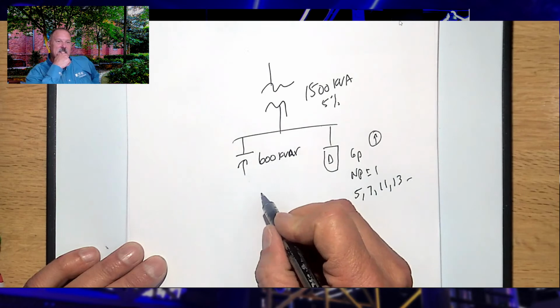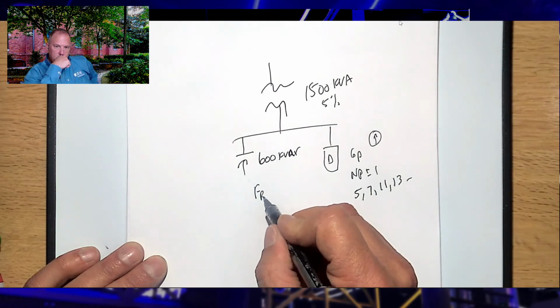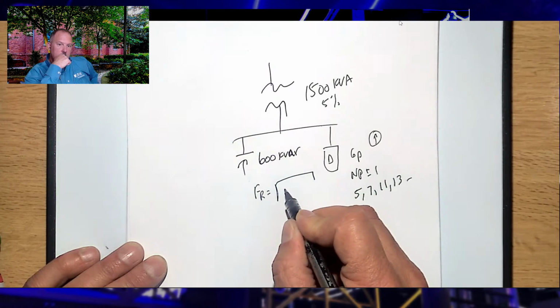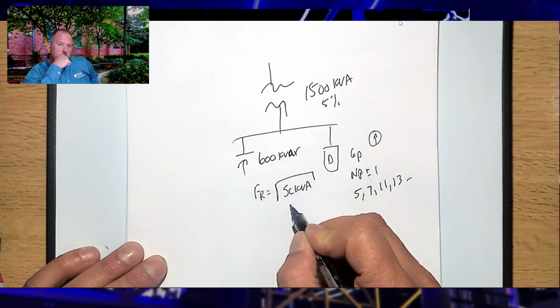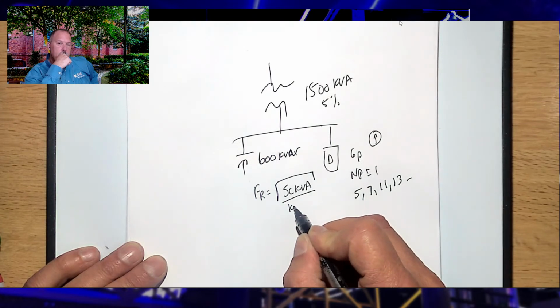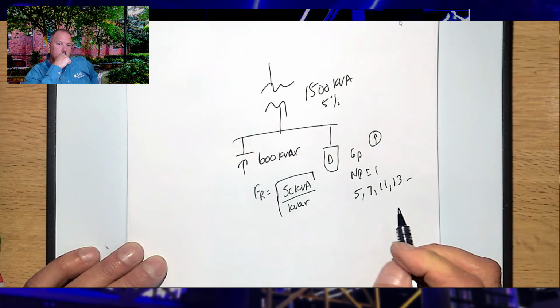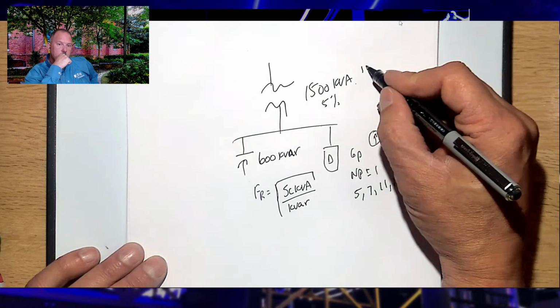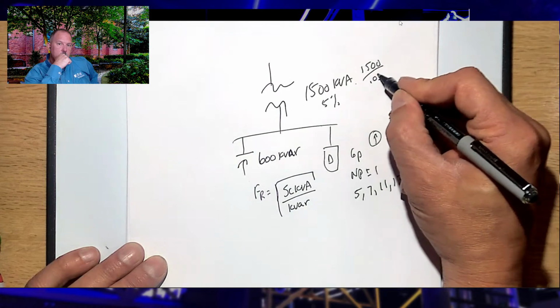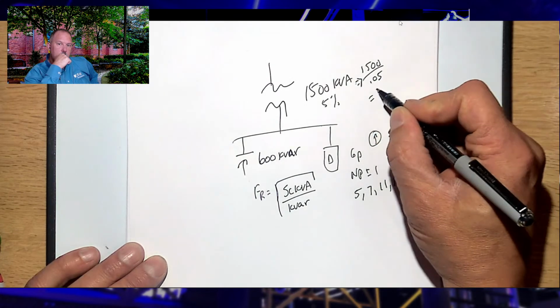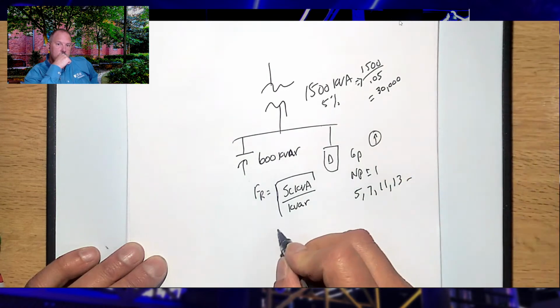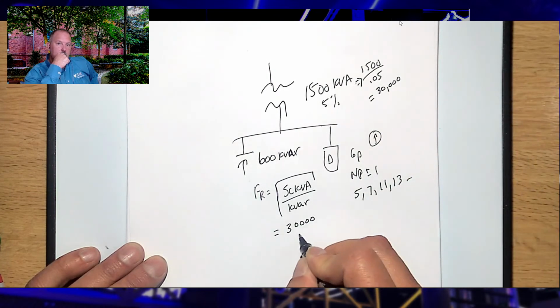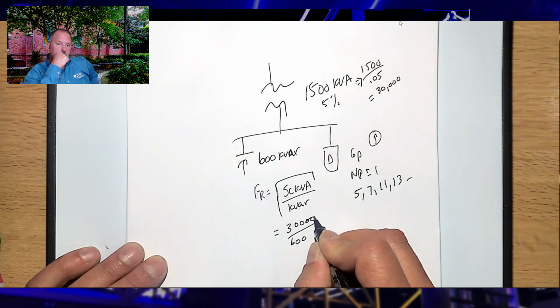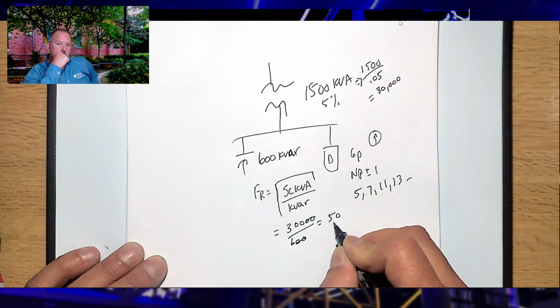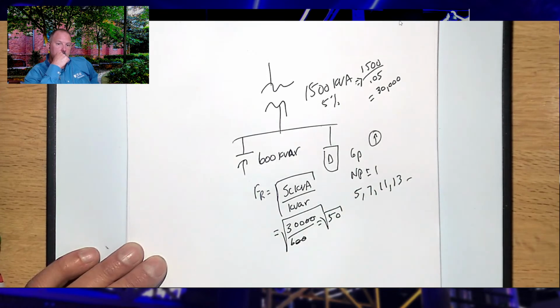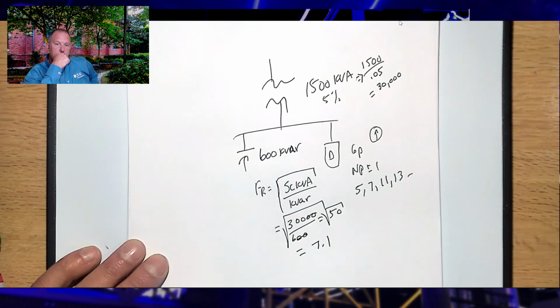So my resonance point, my frequency of resonance, is the square root of the short circuit kVA over kVAR. Okay. And my short circuit kVA, just like we do for fault calculations, is 1,500 over 0.05, which is 30,000. Okay. So 30,000 divided by 600. So if I cross that off, I get 50. I take the square root of 50. That turns out to be what, 7.1 or something like that? Yeah.